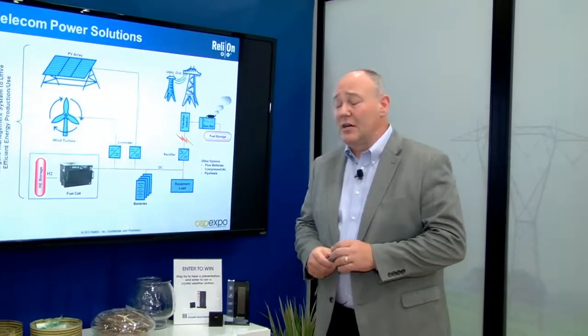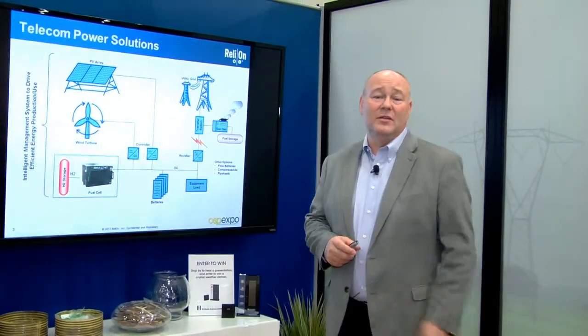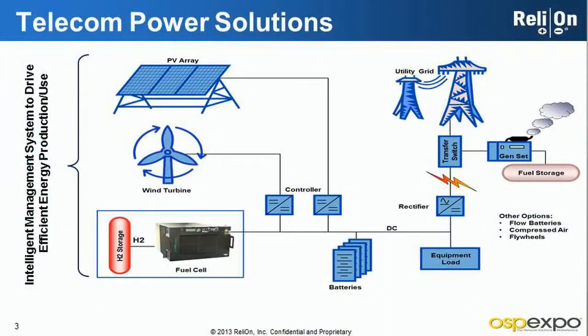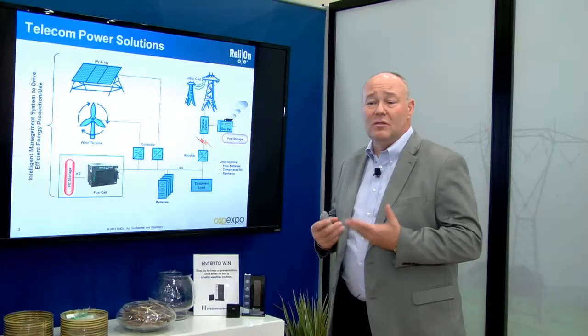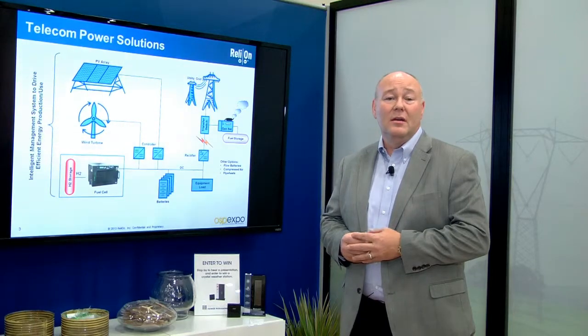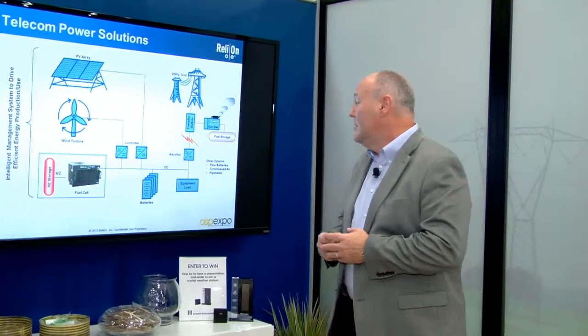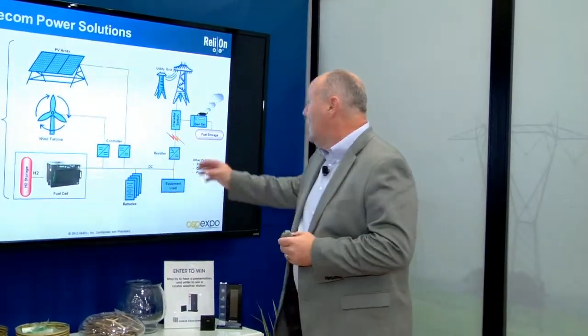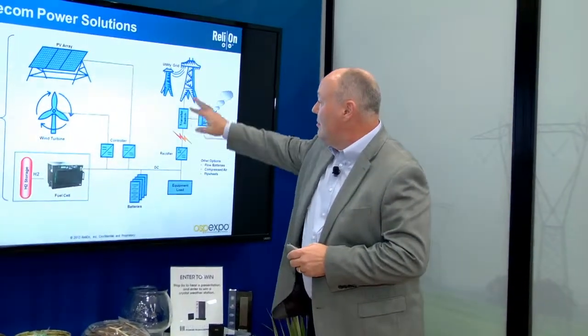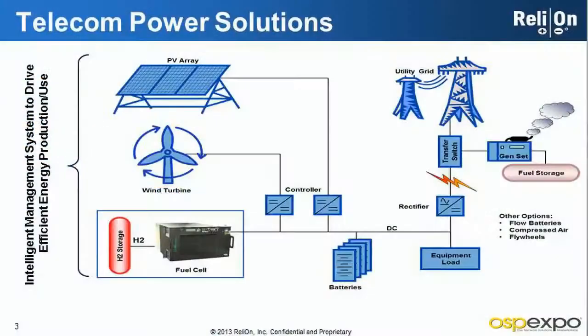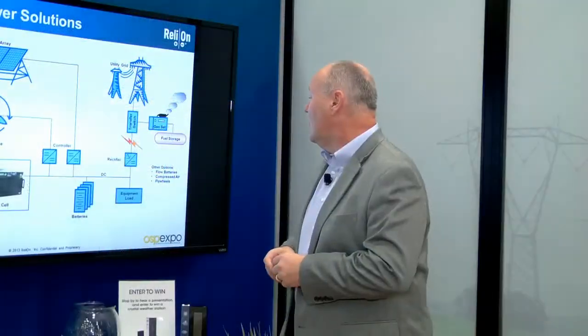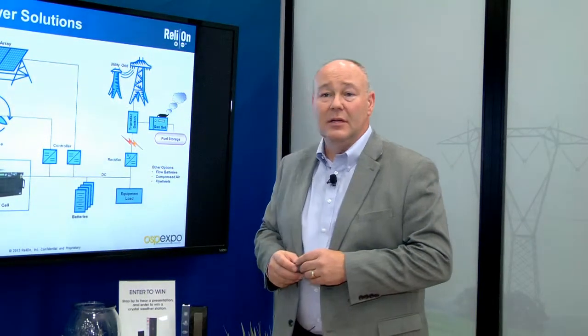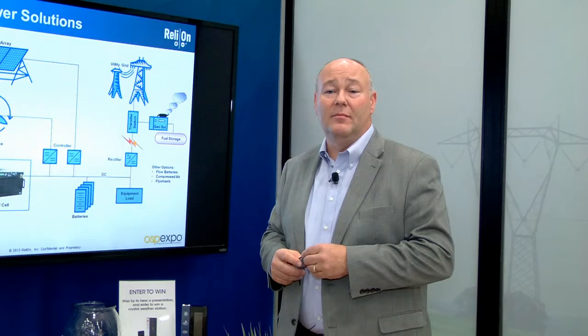A telecom power system is made up of several components, and this illustrates the various devices that could be used to power the network. The traditional model is the utility grid feeding in through a rectifier system to feed the DC load, directly to the equipment load, supplied with a diesel backup generator. That model is used the world over and is very capable of providing all the power needs.